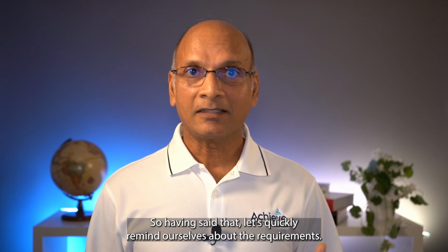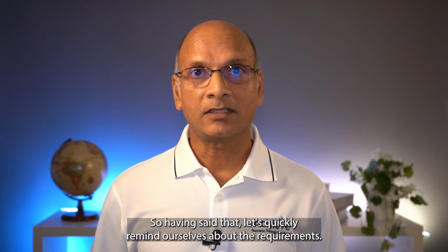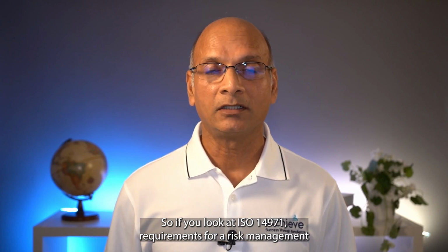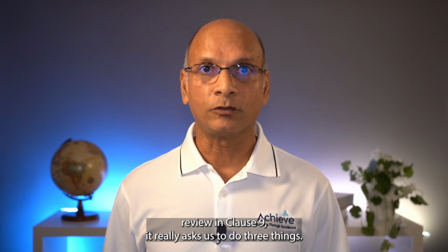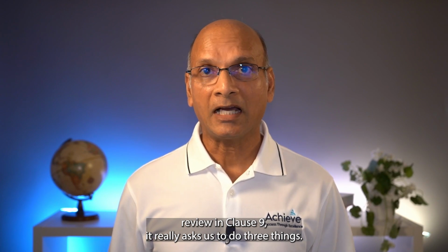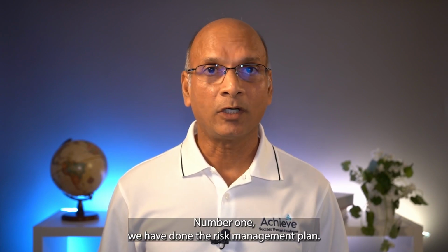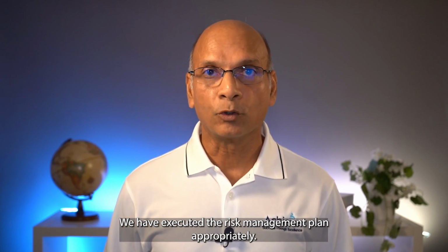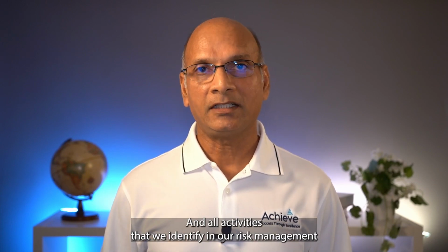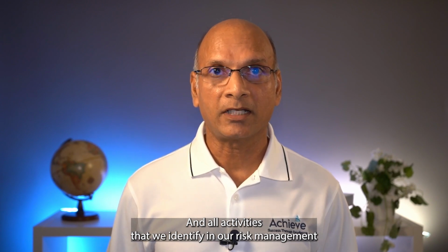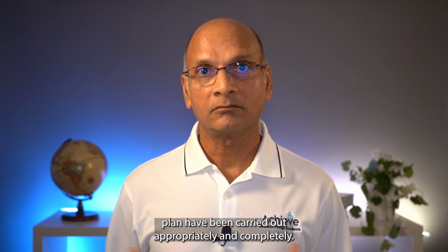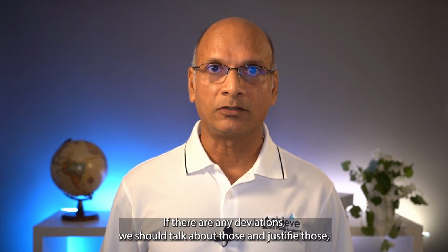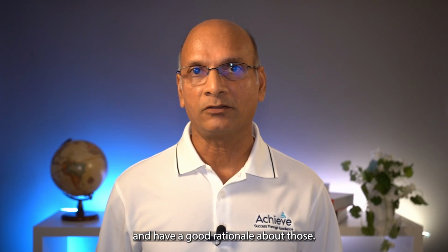So having said that, let's quickly remind ourselves about the requirements. If you look at the ISO 14971 requirements for a risk management review in clause 9, it really asks us to do three things. Number one, we have done the risk management plan. We have executed the risk management plan appropriately, and all activities that we identified in our risk management plan have been carried out appropriately and completely.